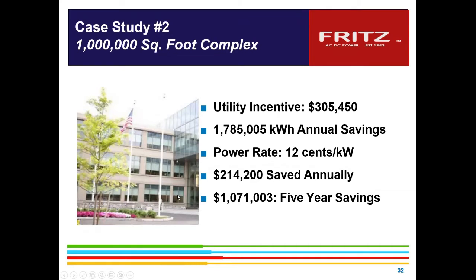This happened to be a 1,000,000 square foot complex that we had done. Originally they said, okay, we have multiple motors in our building, but we've already put drive controls on. Well, we went in and did an audit on the building and found about another 75 motors that all needed controls in the right spot. So we were able to secure an incentive of about $305,000 for them, and about 1,785,000 kilowatt hours saved annually, about $200,000 of annual savings, about $1 million over 5 years. So it's definitely worth a deep dive into your electric motors, and we have many partners around the world that can do the proper installation. We help get the review.